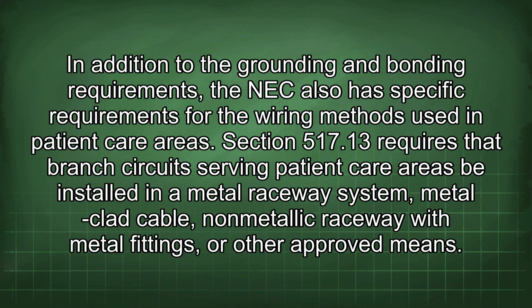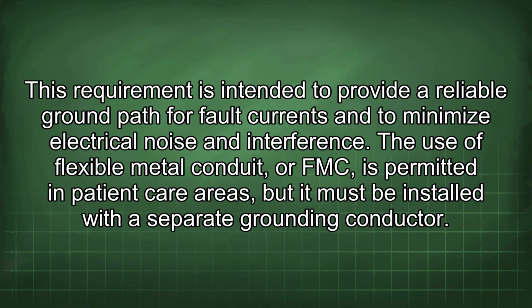In addition to the grounding and bonding requirements, the NEC also has specific requirements for the wiring methods used in patient care areas. Section 517.13 requires that branch circuits serving patient care areas be installed in a metal raceway system, metal clad cable, non-metallic raceway with metal fittings, or other approved means. This requirement is intended to provide a reliable ground path for fault currents and to minimize electrical noise and interference.